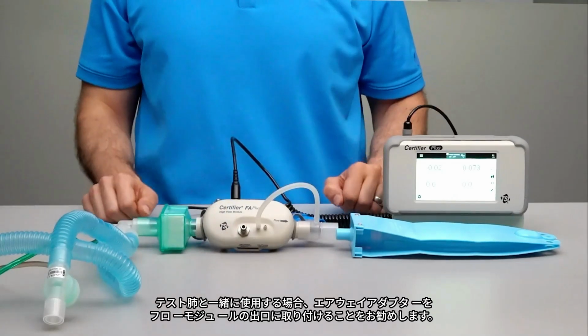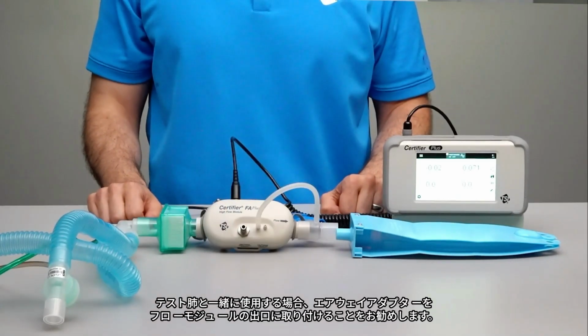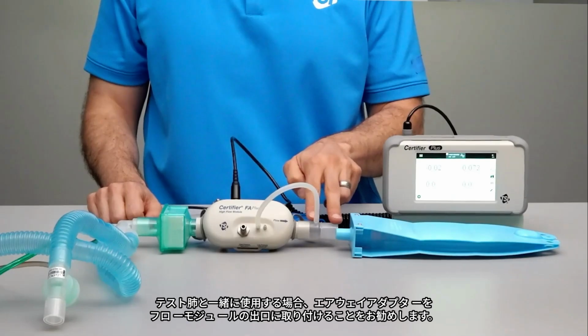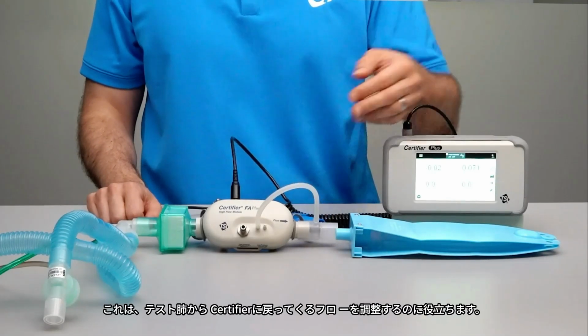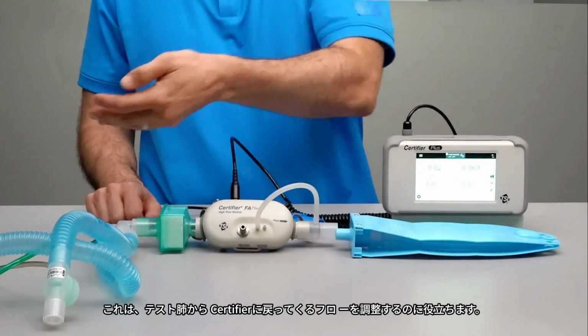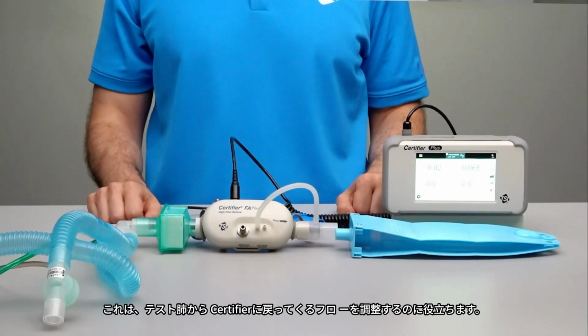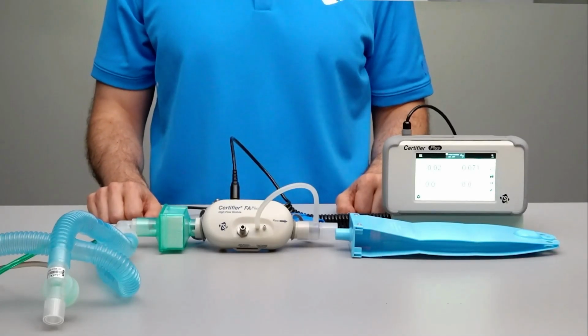When used with a test lung, we recommend that the airway adapter be placed on the outlet of the flow module, as this will help condition the flows that are coming back from the test lung through the certifier.